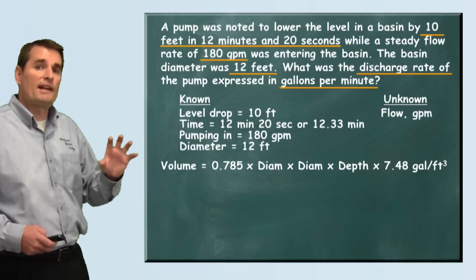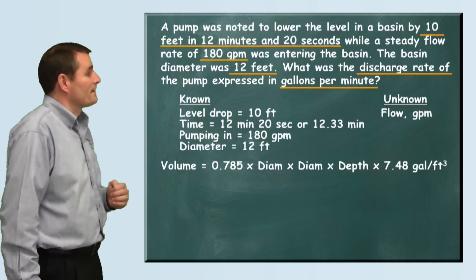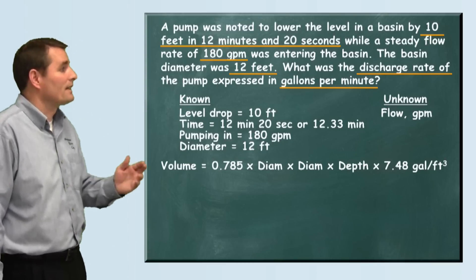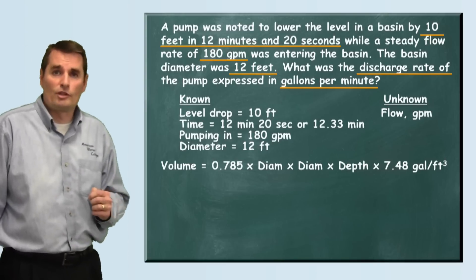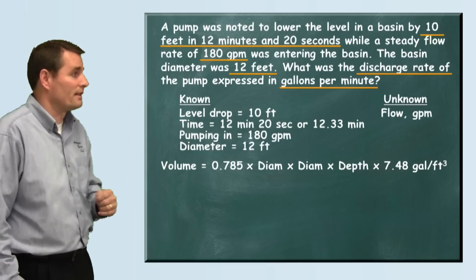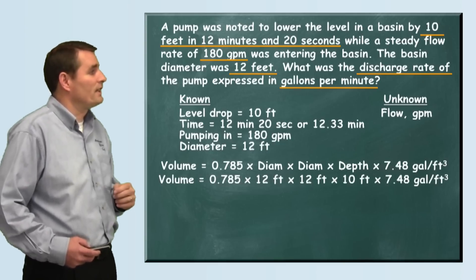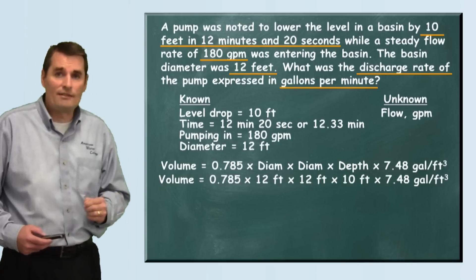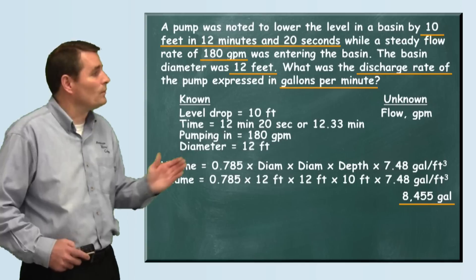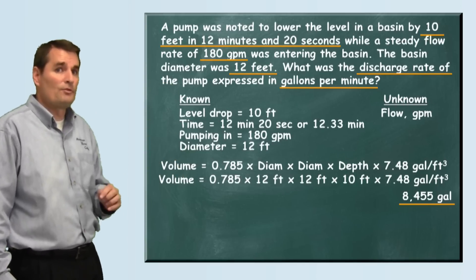We first need to find the volume of the level drop. We use the volume formula: 0.785 times the diameter times the diameter times the depth times 7.48 gallons per cubic foot. This gives us the total volume drop during this 12.33-minute period. Plugging in our diameter of 12 feet and our depth drop of 10 feet, we find that the total volume was 8,455 gallons.